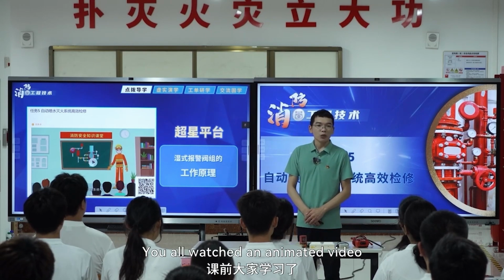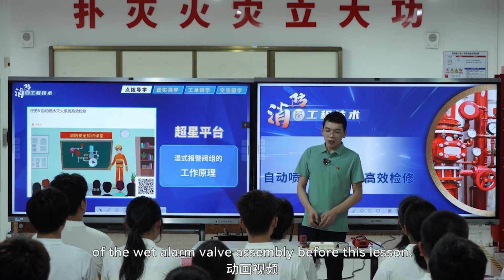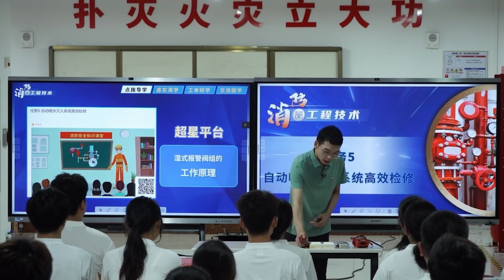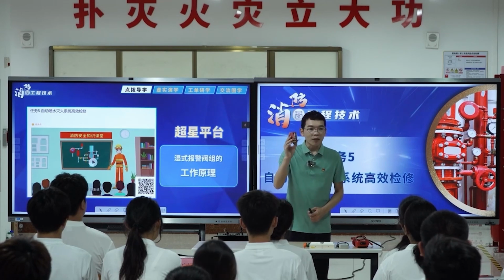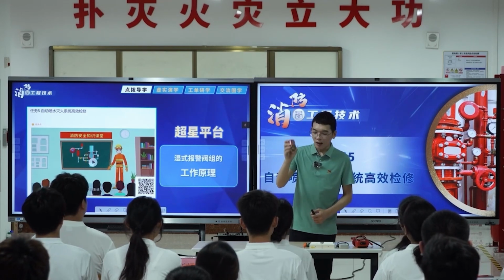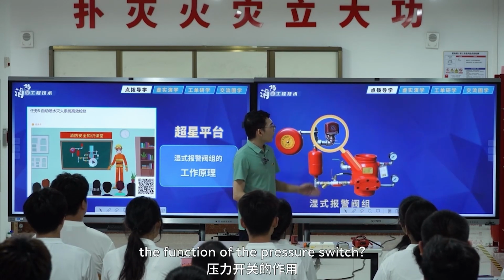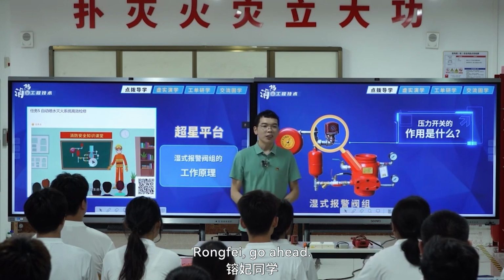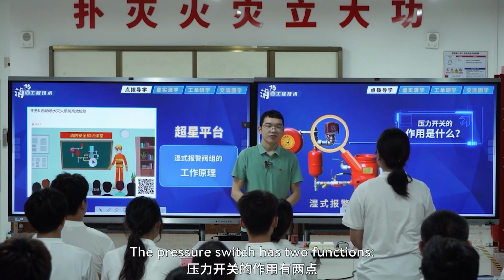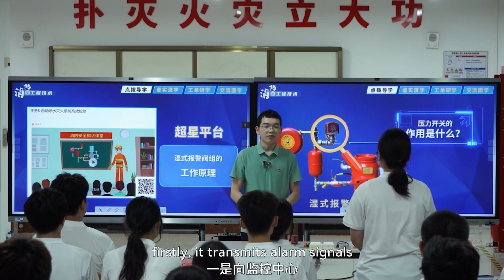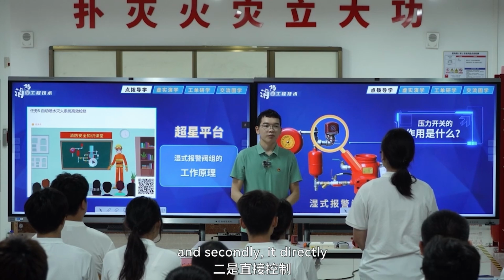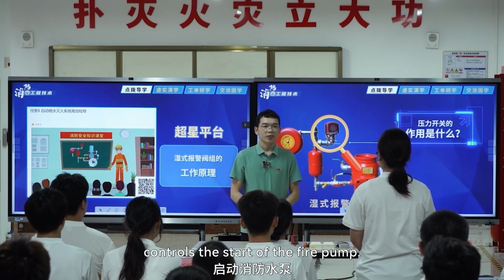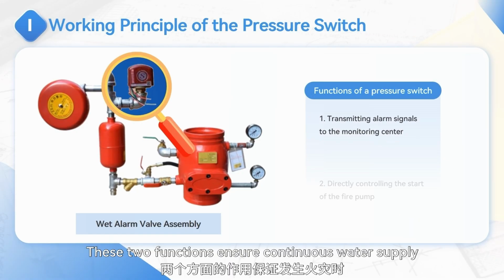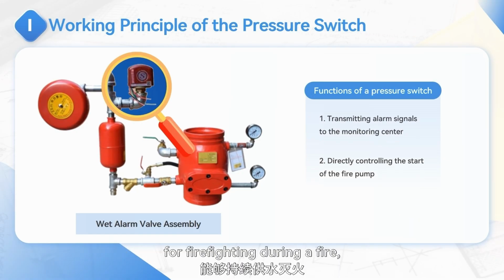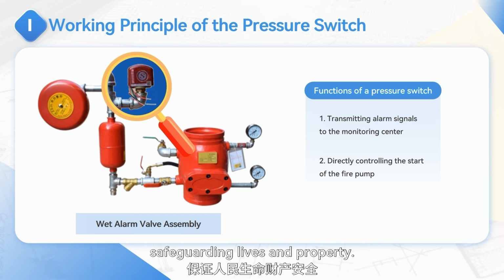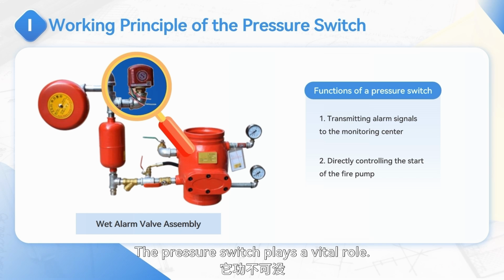You all watched an animated video explaining the working principle of the wet alarm valve assembly before this lesson. Can anyone recall what this component is? The pressure switch. Excellent. Who can explain the function of the pressure switch? Romfei, go ahead. The pressure switch has two functions. Firstly, it transmits alarm signals to the monitoring center, and secondly, it directly controls the start of the fire pump. Correct. These two functions ensure continuous water supply for firefighting during a fire, safeguarding lives and property. The pressure switch plays a vital role.